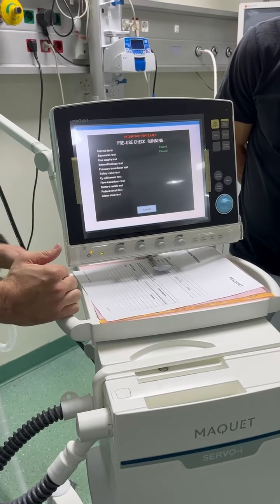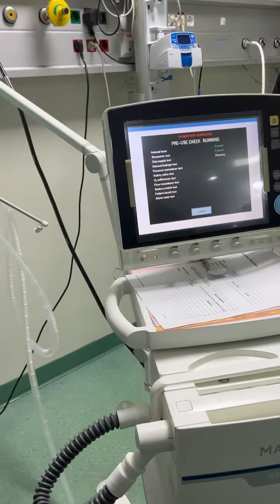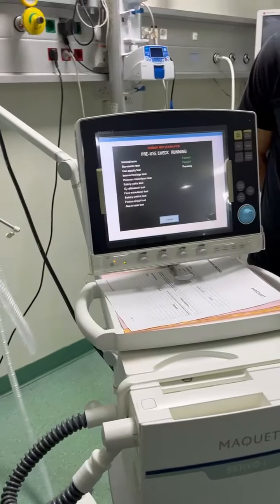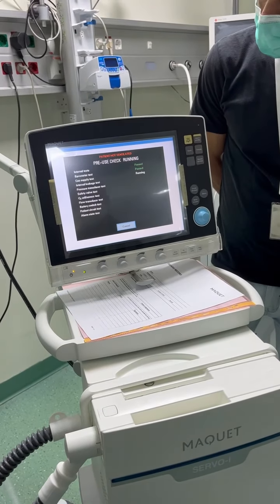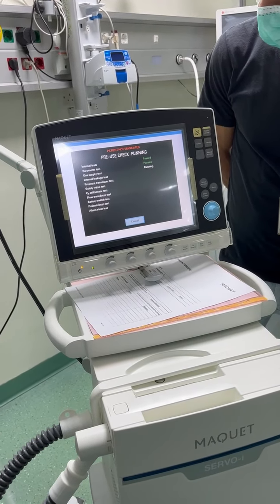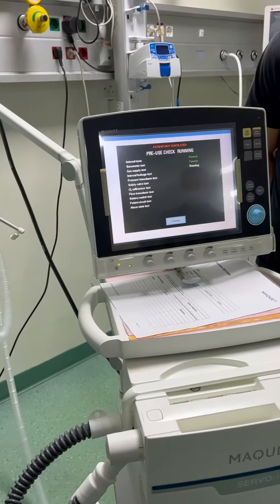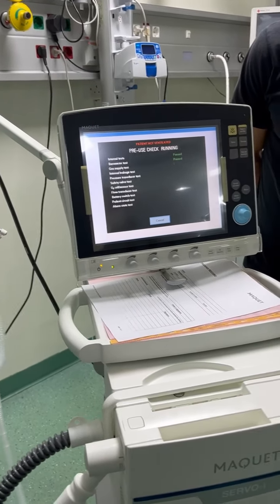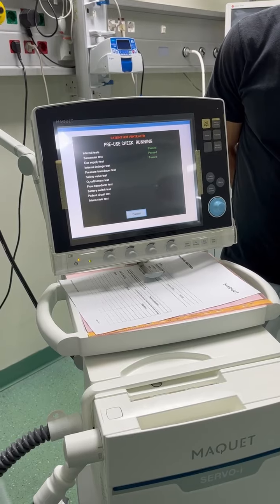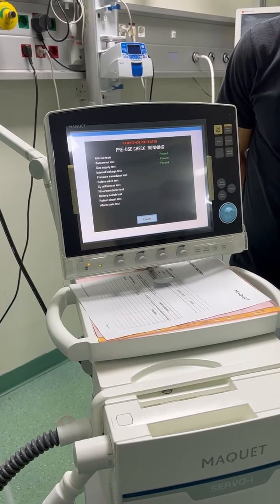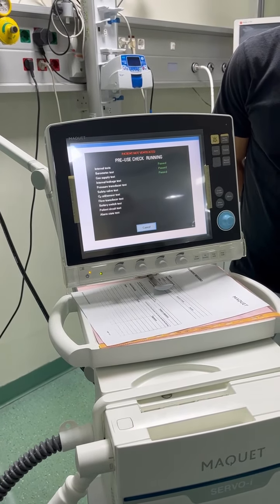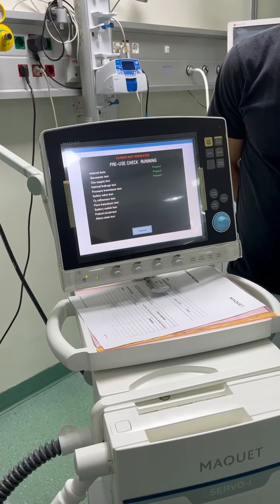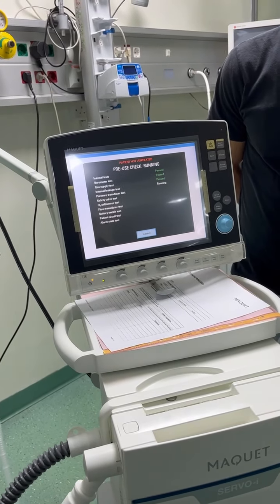And as I said, it has to be connected with the circuit that you will use on the patient. The same. Why in this one, even if it's the same company? Because each circuit has its own compressibility, its own compliance. So the machine will do the measurements and it will compensate for the dead space of the circuit. So in order to do it, it has to be done on the same circuit. Okay?